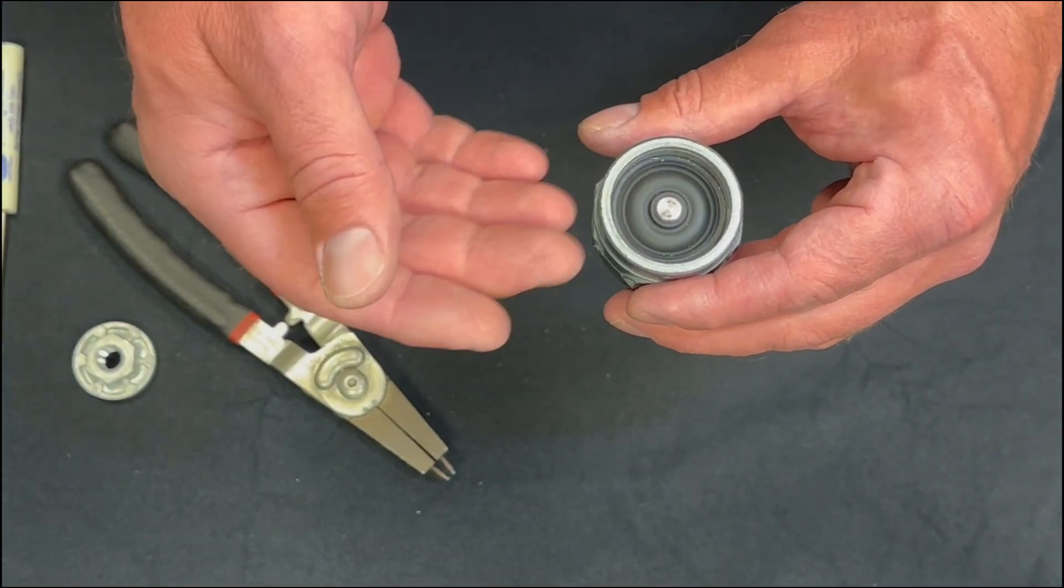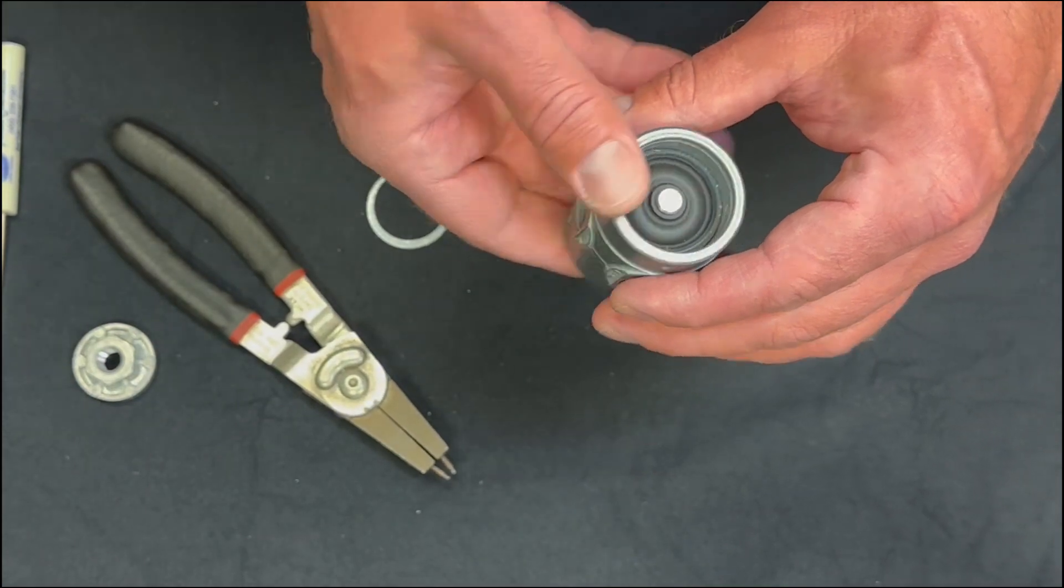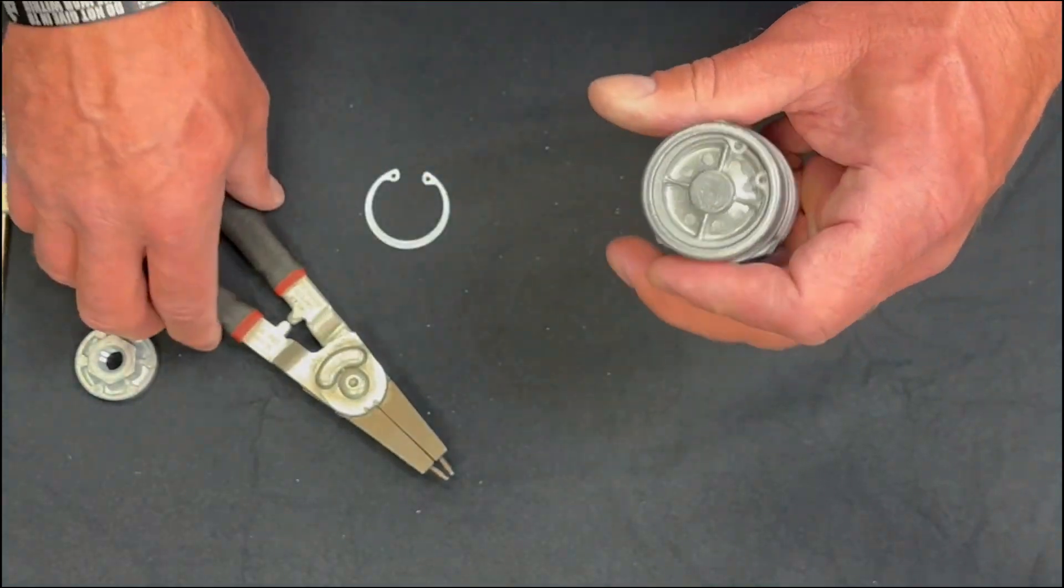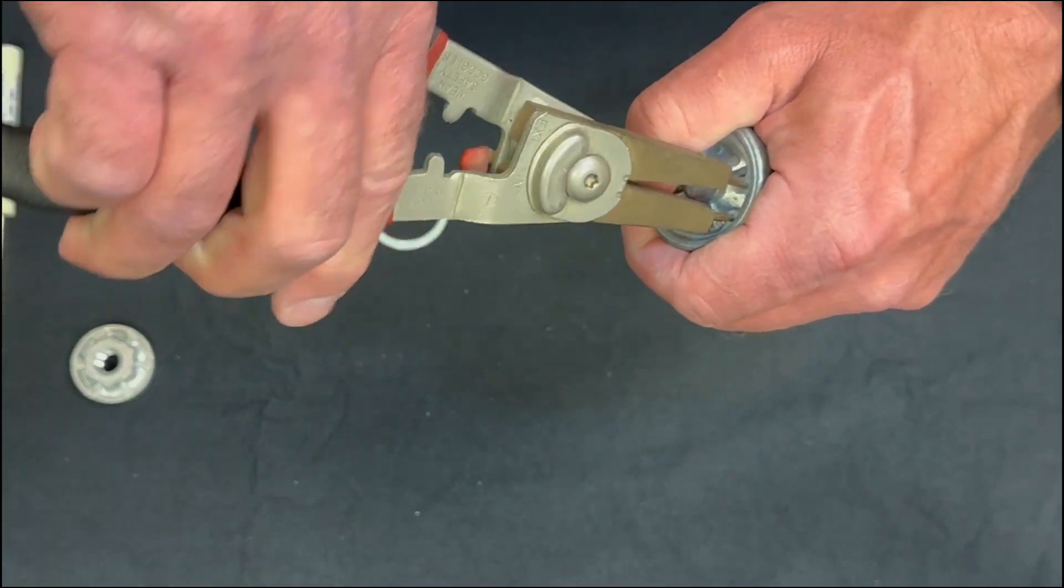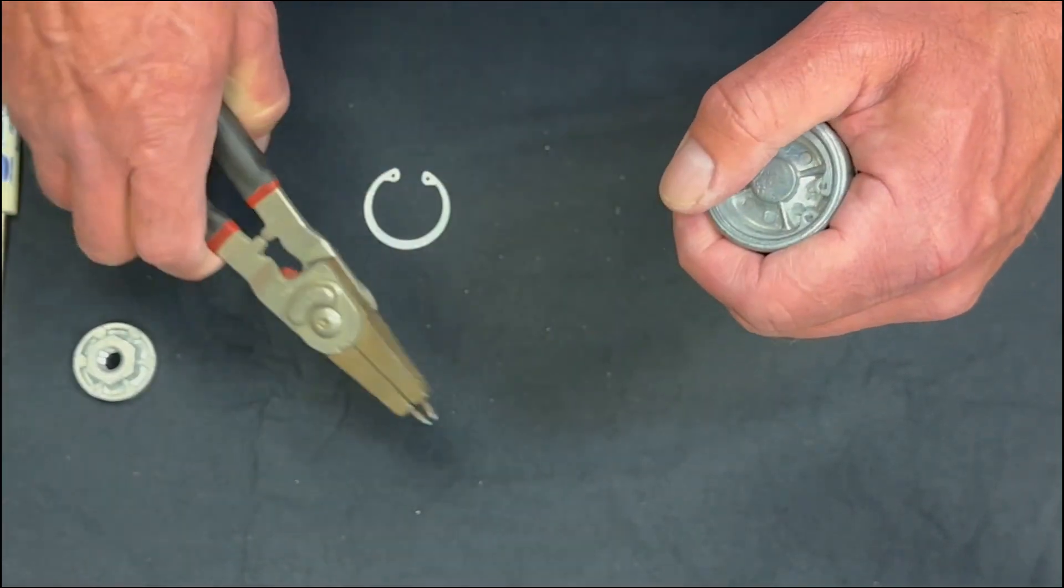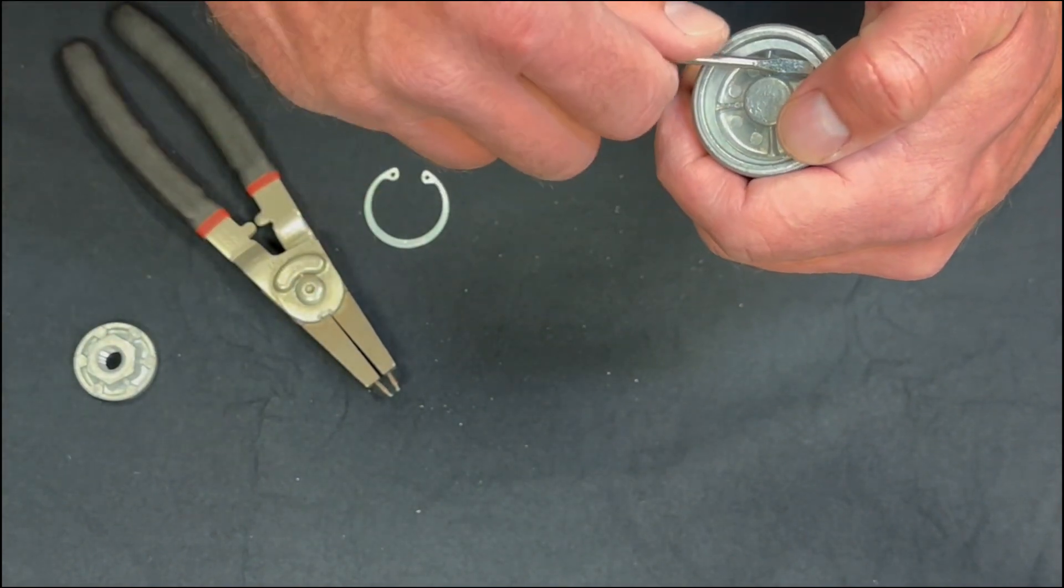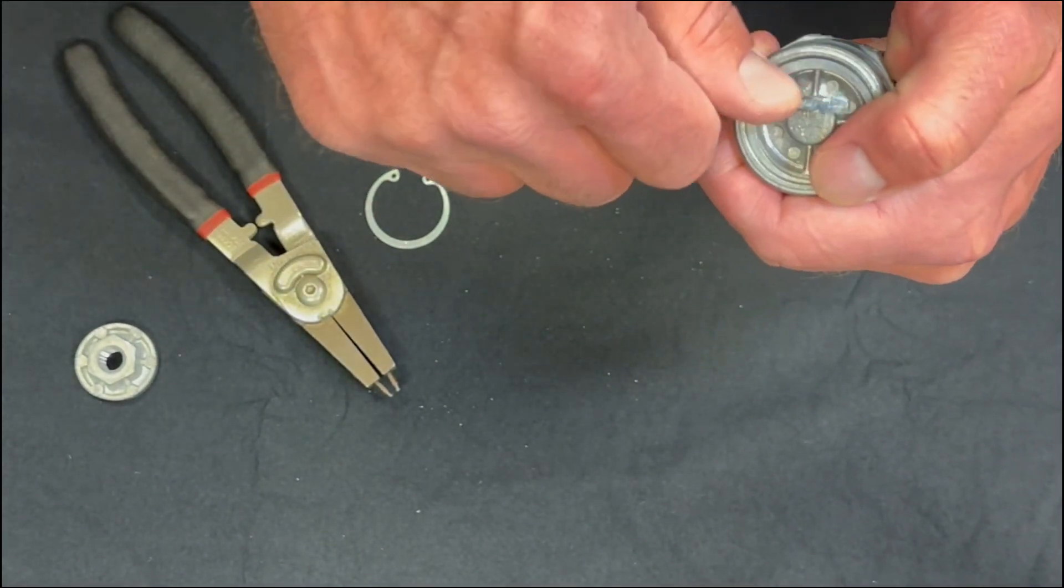If the diaphragm and everything looks good inside, the next thing you can do is flip it over and remove the snap ring on the bottom portion of the pilot valve as well, maintaining the same procedure as the top so that you don't lose the snap ring.